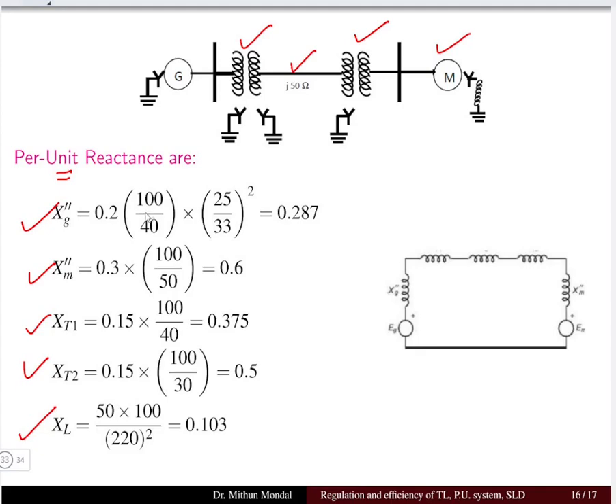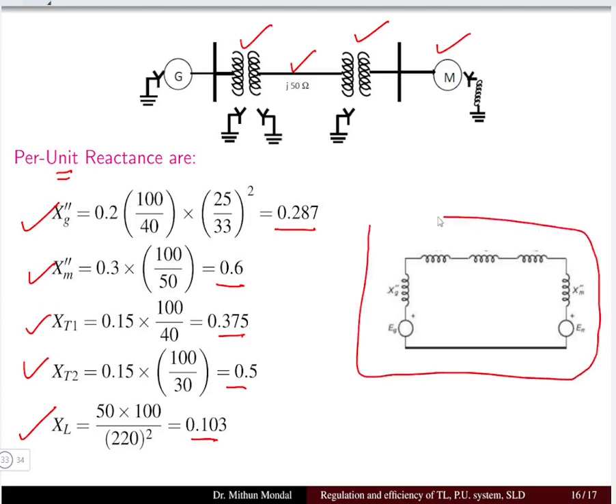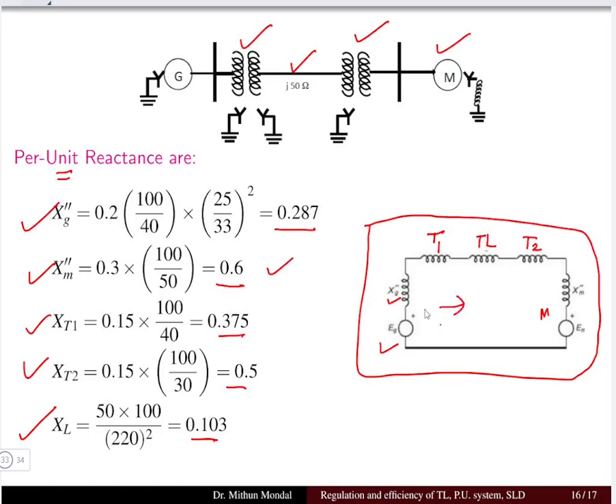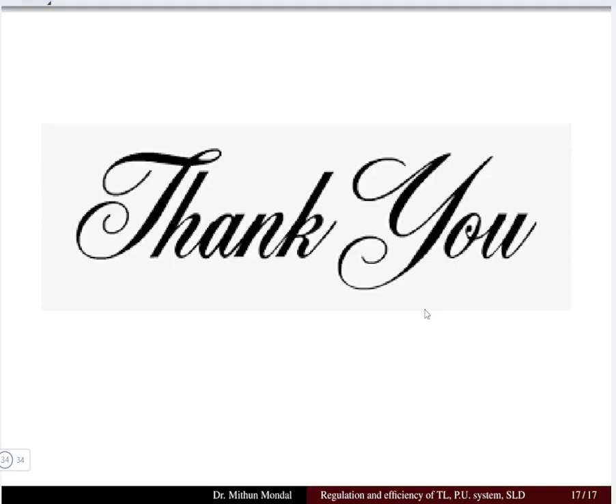Once all per unit reactances are obtained, the reactance diagram is drawn: starting from the generator voltage EG in series with the generator reactance, then transformer T1, then the transmission line reactance, then transformer T2, and finally the motor with its reactance. All computed per unit reactances are substituted into the diagram to complete the solution.